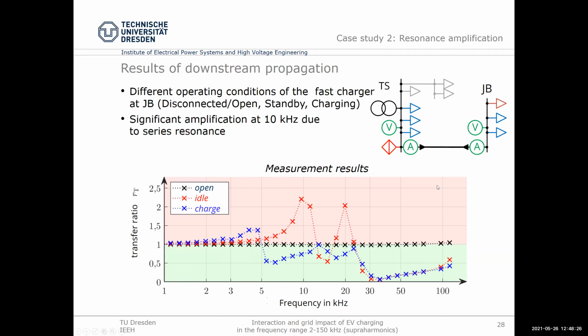The fast charging station had two more operating states in addition to disconnected or off: a standby stage and a charging stage. In standby or idle mode, shown with red crosses, we could indeed see a significant resonance amplification at 10 kilohertz and again at 20 kilohertz. This is because the Renault Zoe has a 10 kilohertz switching frequency — this is basically the series resonance amplification we observe. If it had a switching frequency of 15 kilohertz, nothing would have happened; nobody would have seen that phenomenon.